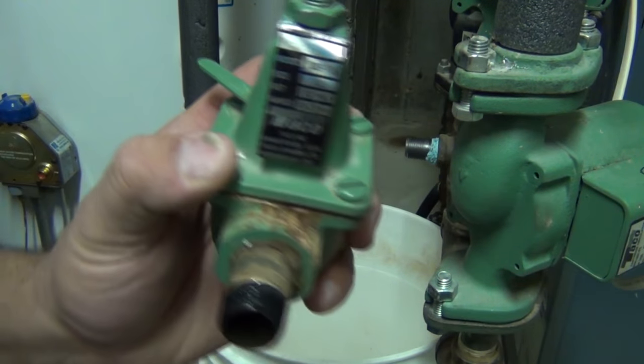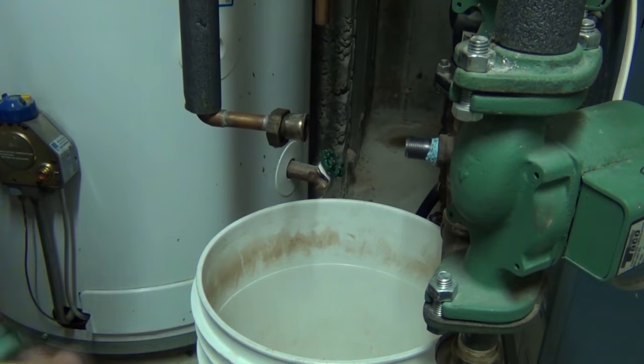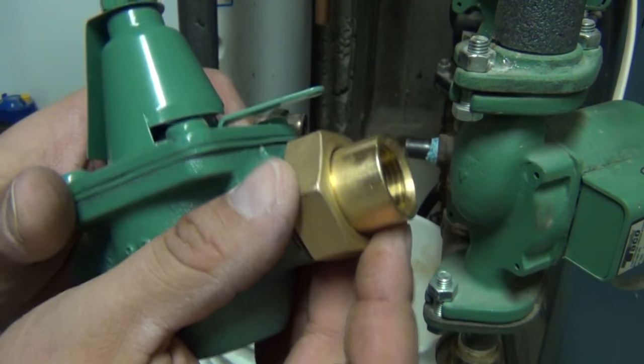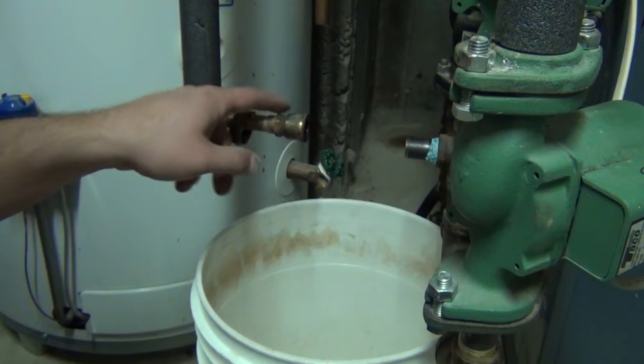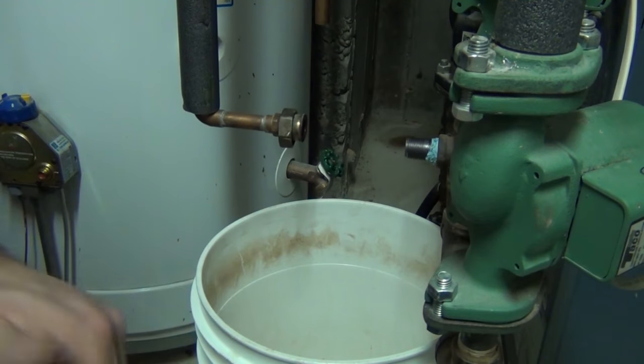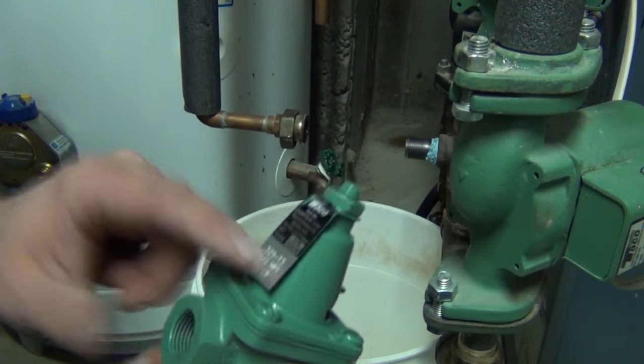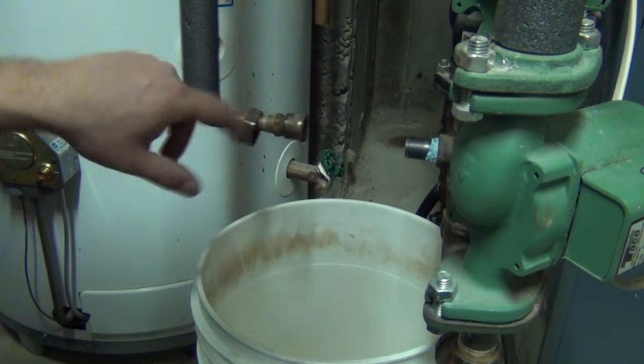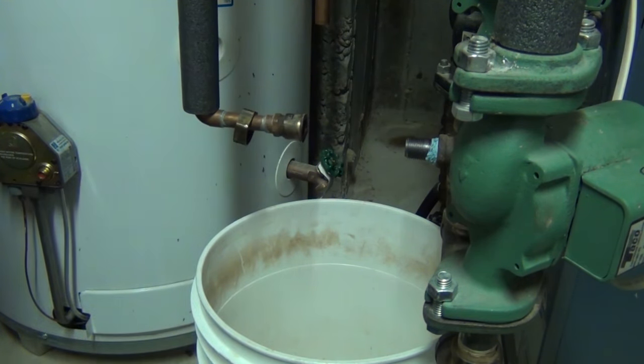This is a Taco 329-T3. The old one I had was a 329-3. The difference between the 3 and the T3 is just the union — on the T3 it's threaded, but the 329-3 has a sweat union. In our case I'm going to be reusing the old union, so the included union on the new valve we're not even going to use. The valve itself is identical, so if all you can find is a T3 and you need a straight 3, they're both the same.